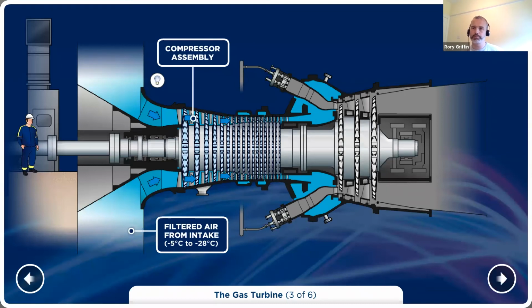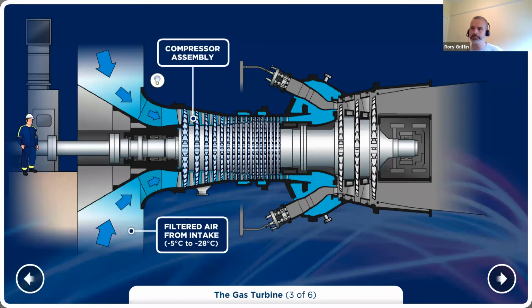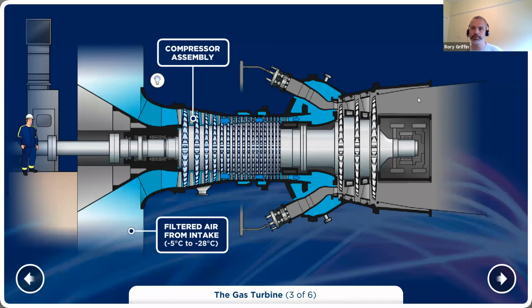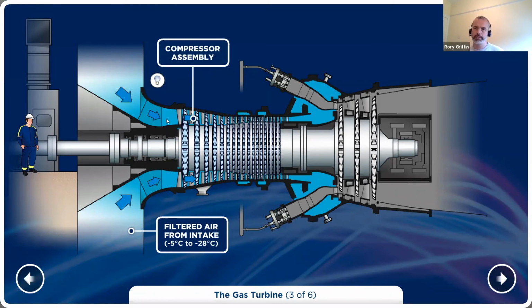That mightn't sound like much, but when you add up the weight of the gas turbine, the rotor of the generator, and the steam turbine, you've about 300 tons spinning at 3000 RPM. And in a couple of milliseconds, you've taken 30 off. So that's huge mechanical stresses on the couplings. So we had to demonstrate the machine could take that.